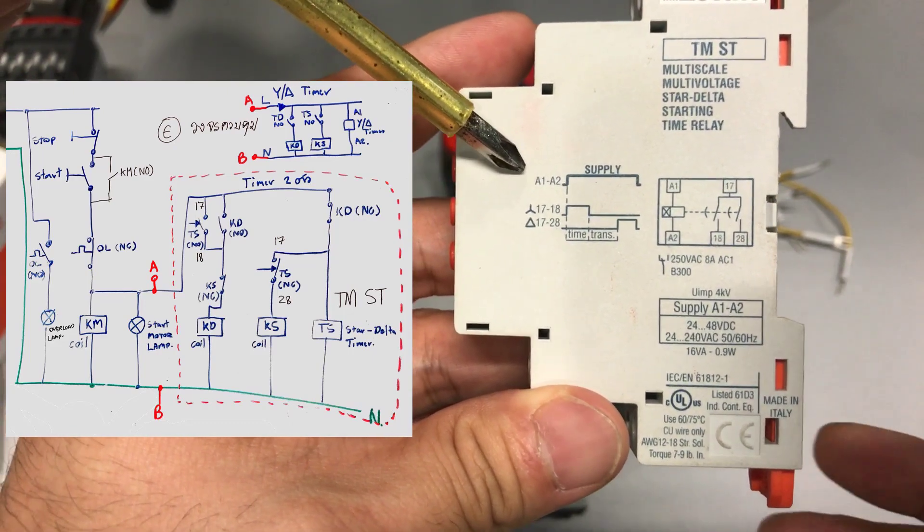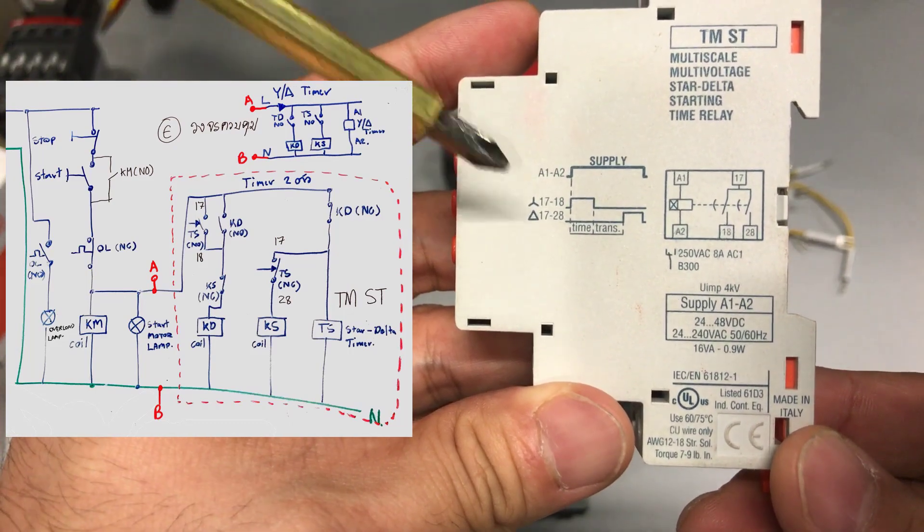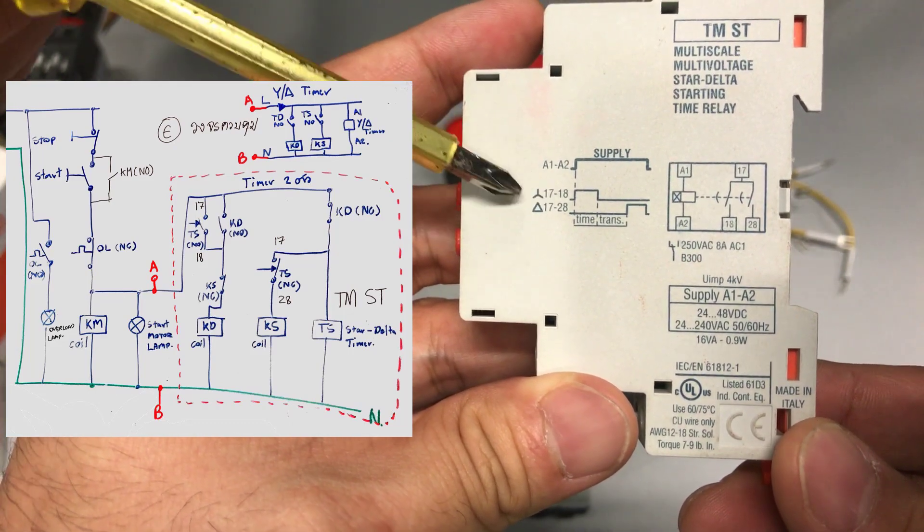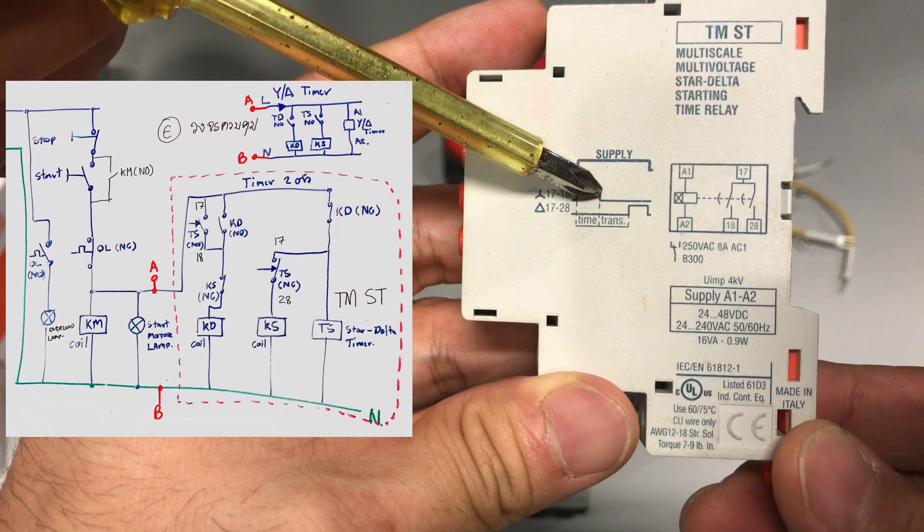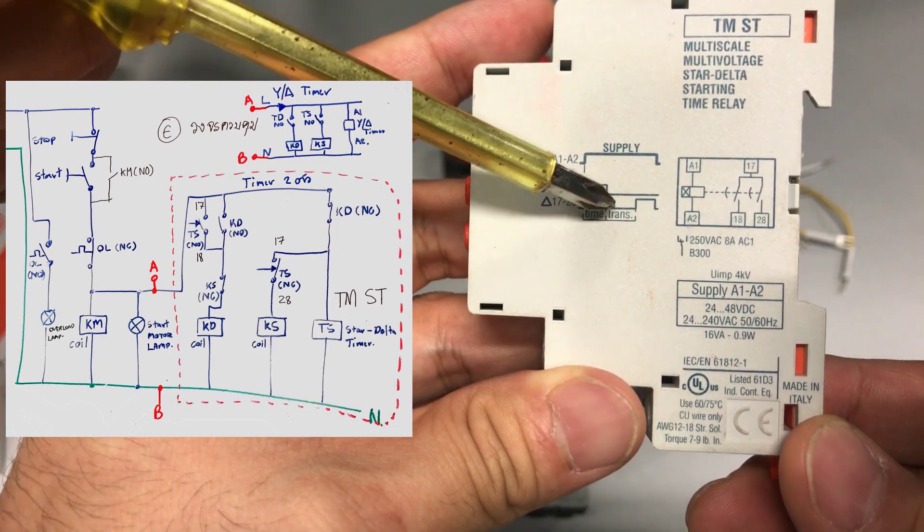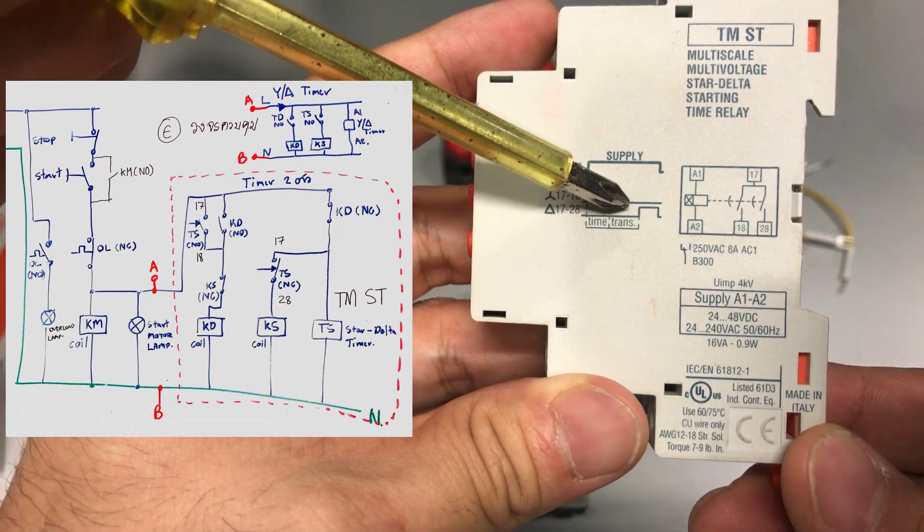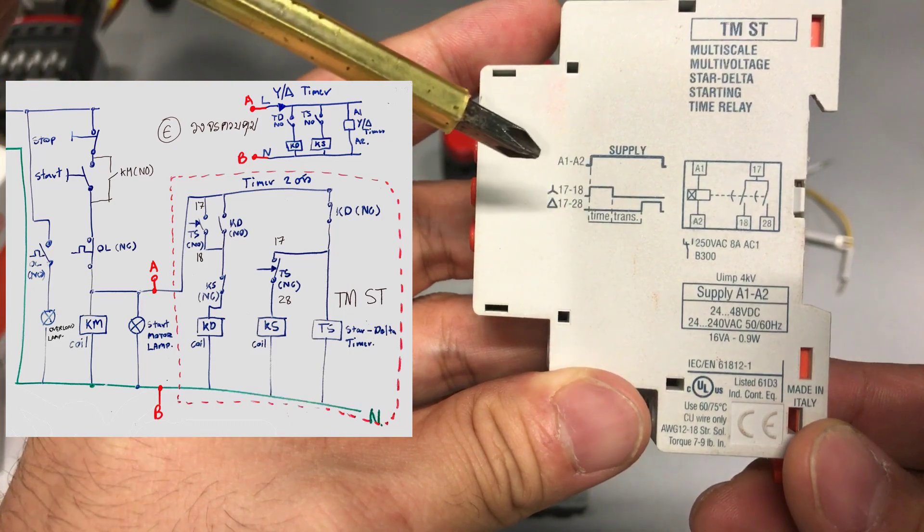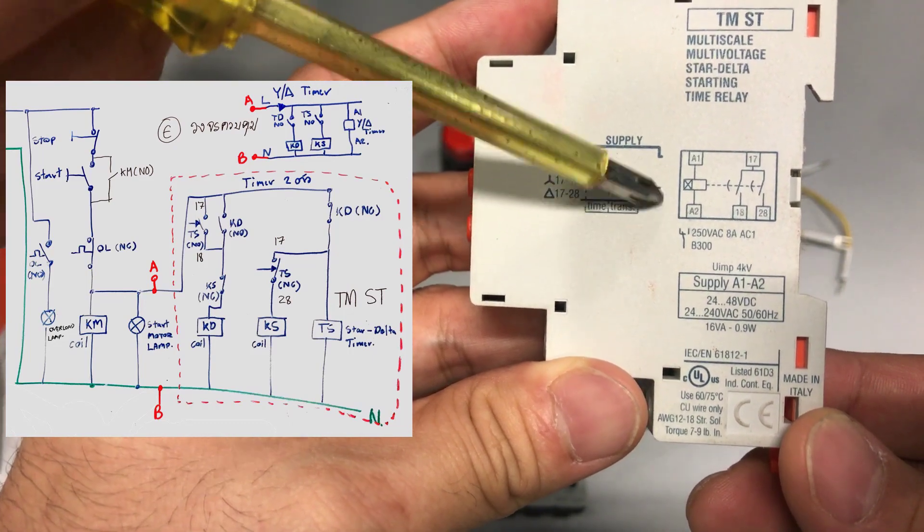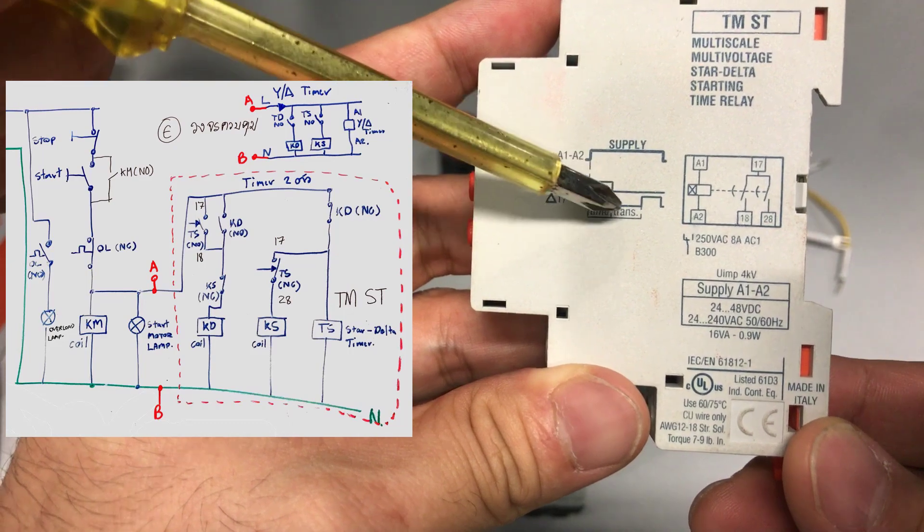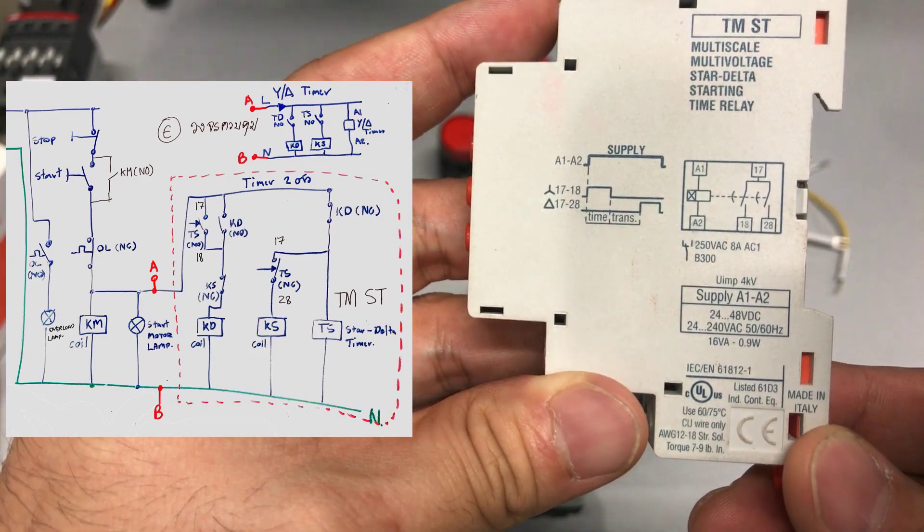As you supply the current from A1 to A2, the star contactor will start first. Then there will be a transition delay. We can set the value of this, then the delta contactor will start. The transition function prevents both the star and delta contactor from working at the same time.